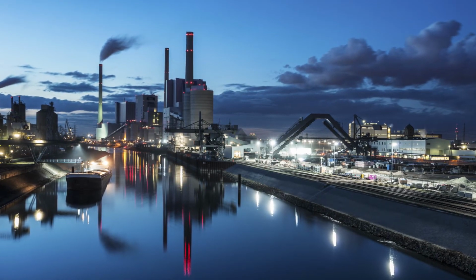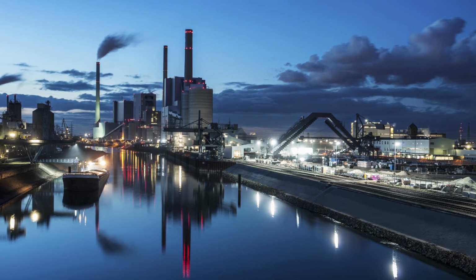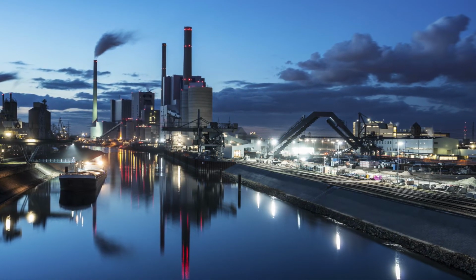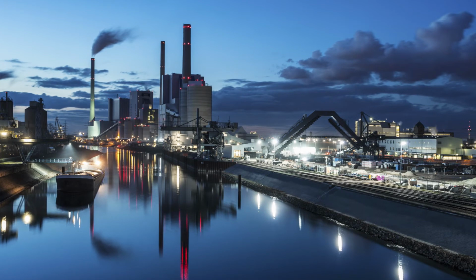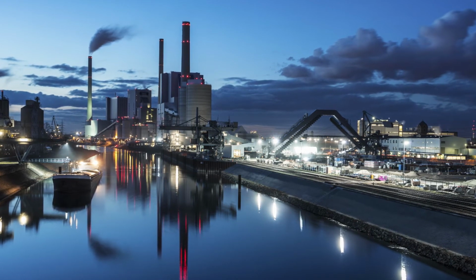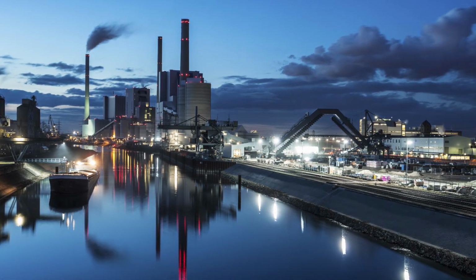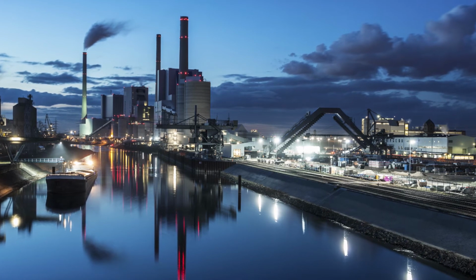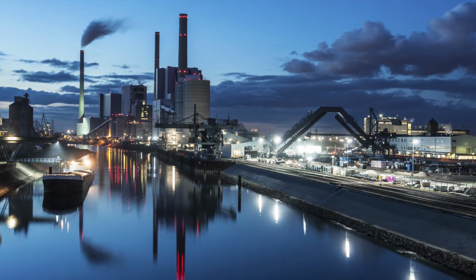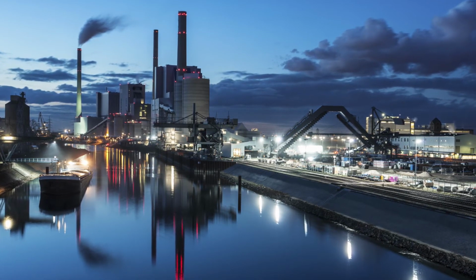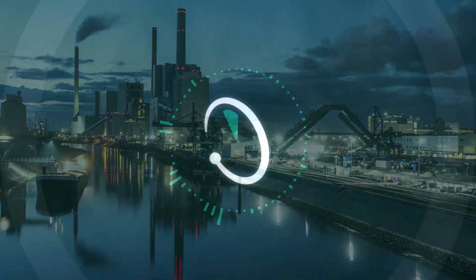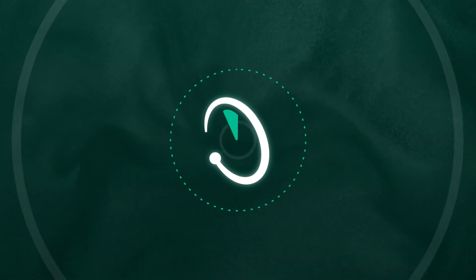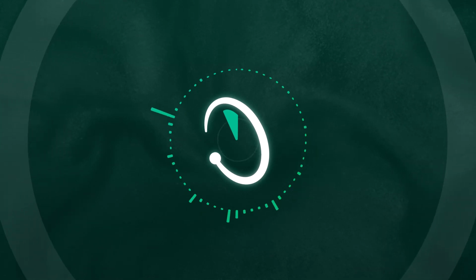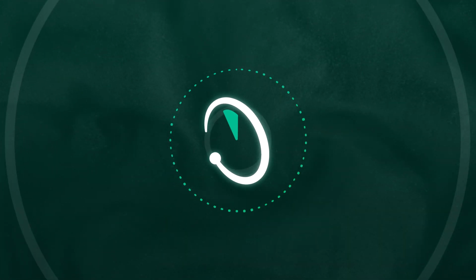It will not forward that information onto a system one or a DCS. It will, however, send a message that, hey, I woke up to take a reading, but it looks like the machine was off. So at least the sensor is still reading. And of course, if it's above that vibration level, it will happily carry on and send that data through. So it's returning a status message: I looked, it didn't appear the machine was running, so we didn't collect any data.